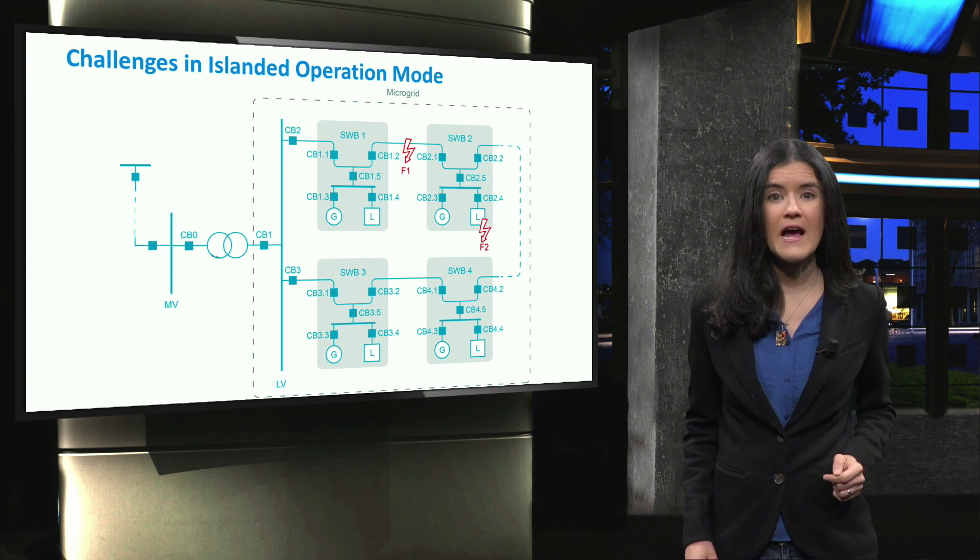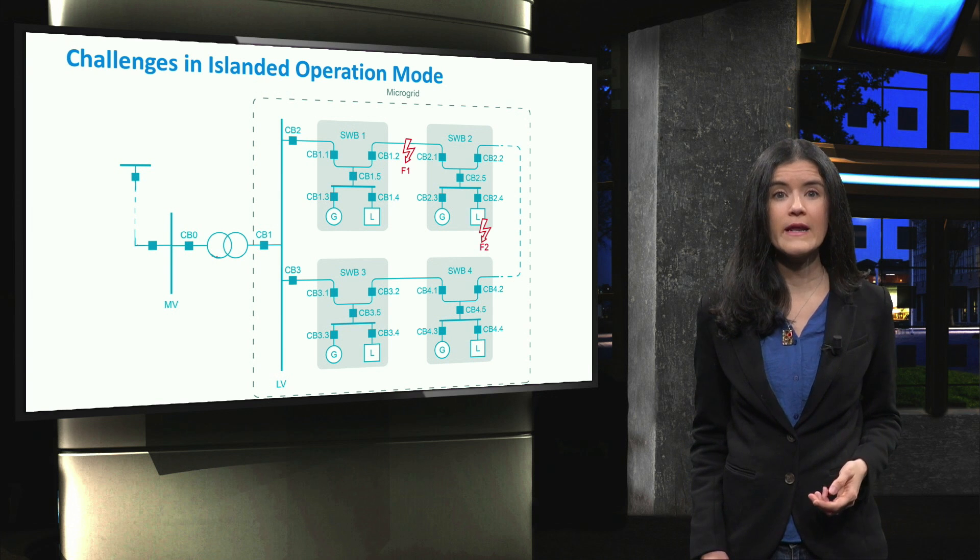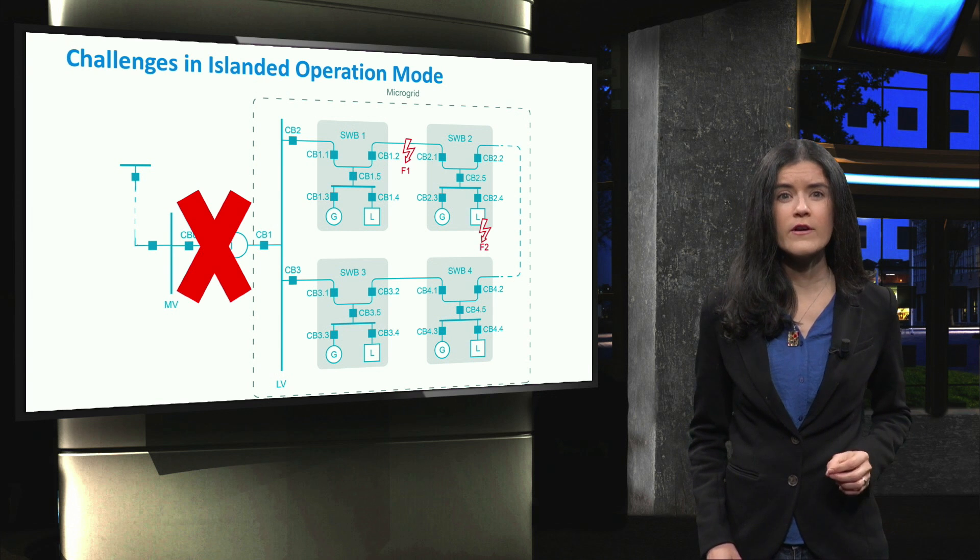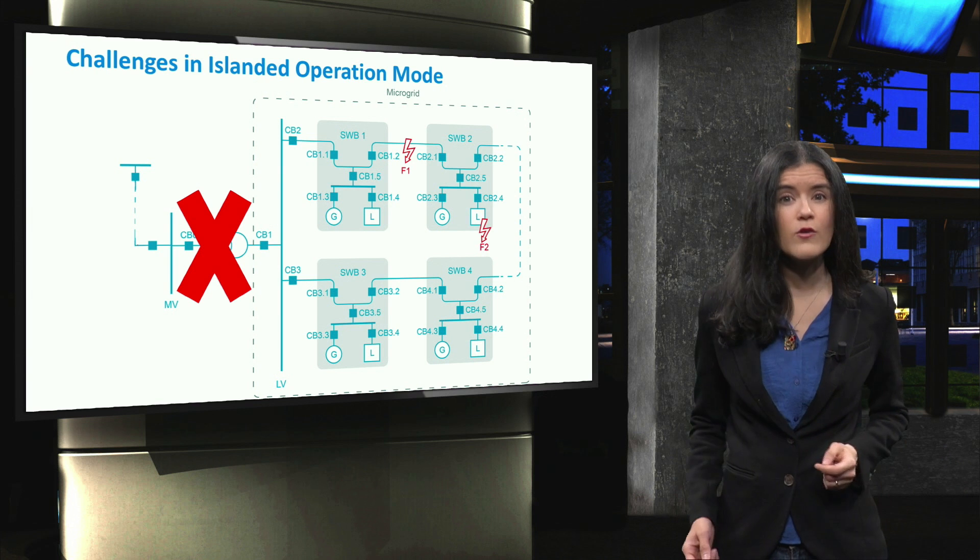This is even more challenging when the microgrid is operating in islanded mode. In this mode, there is no fault current from the main grid, making the overcurrent even lower.